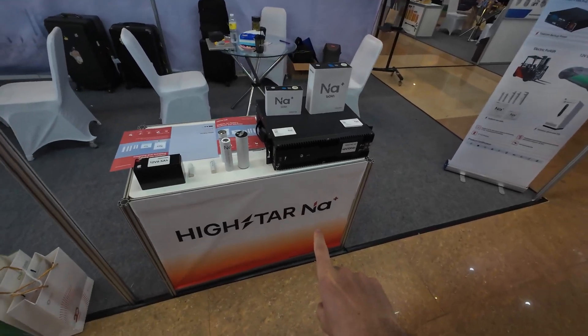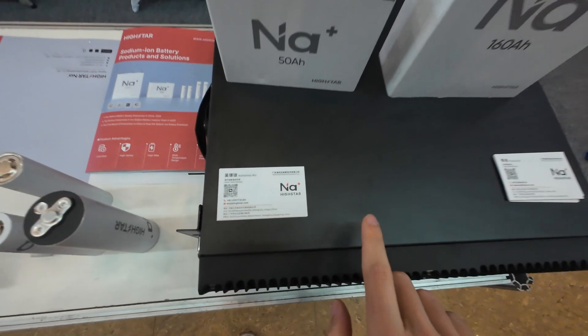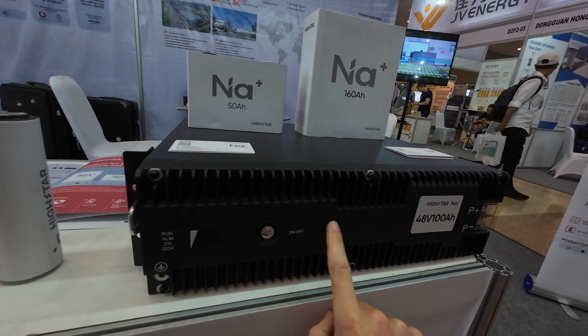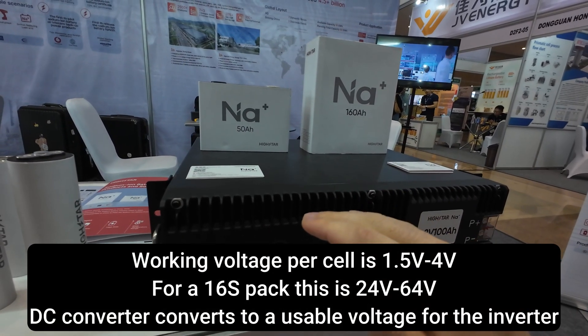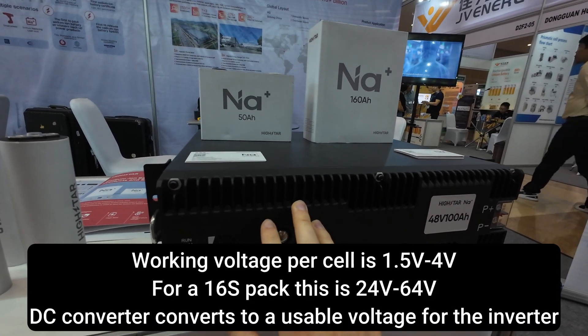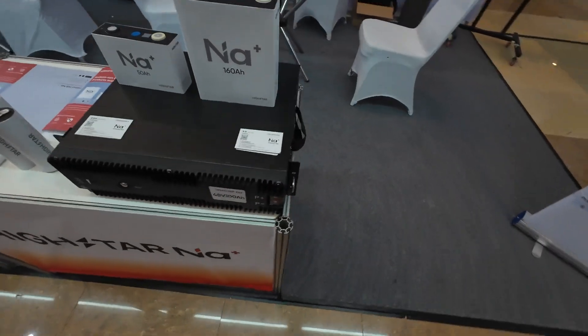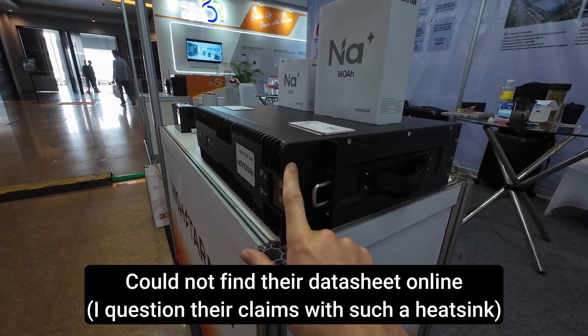We recently talked about sodium cells, and this is a sodium battery from HighStar. They told me there are 16 cells inside the battery. What's interesting is they have a DC-to-DC converter in the front — that's the heatsink you see here. Sodium batteries have a large voltage range compared to lithium iron phosphate, so this section converts the low or high voltage DC to a suitable voltage range for the inverter. They told me the efficiency of this battery is 97% round trip.